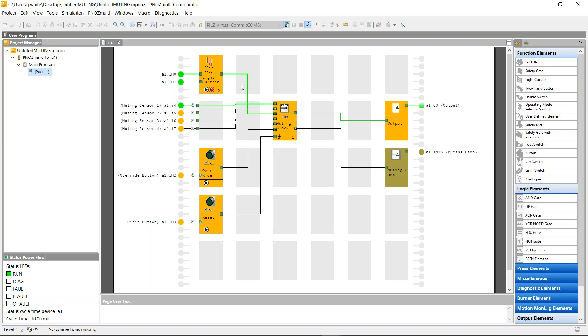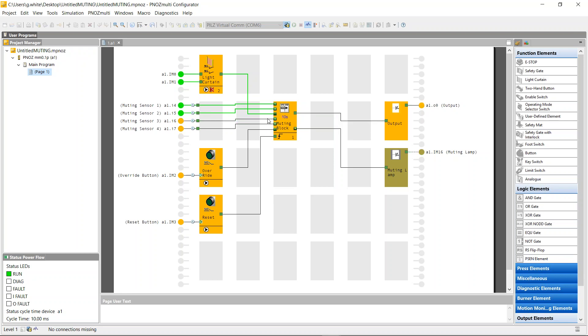But if I was to go muting sensor one, two, three, and four, and then I was to turn off four first, then three, then two, then one, the output has now gone off. So it needs a reset again. So it is quite sensitive, but it has to be.